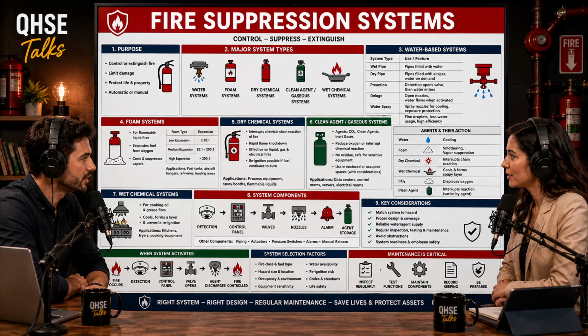So what about photoelectric? That's the other type. Photoelectric detectors rely on optics, specifically something called the Tyndall effect. Inside the chamber, there's a small light source, usually an LED, shooting a beam of light in a straight line. Off to the side, in the dark, is a light sensor. So under normal conditions, the light just shoots straight past the sensor. Exactly. But when visible smoke particles enter the chamber, they physically get in the way of the light beam. Oh, and they scatter the light. Yes. They scatter and reflect the light in all directions, including onto the sensor that was previously in the dark. Once the sensor detects that scattered light, it trips the alarm.